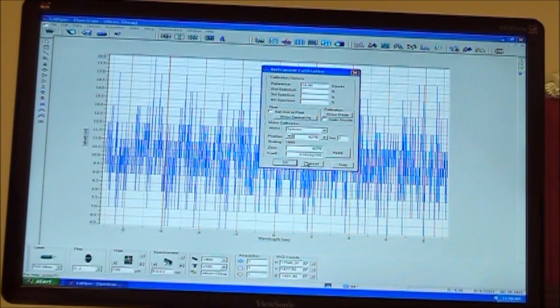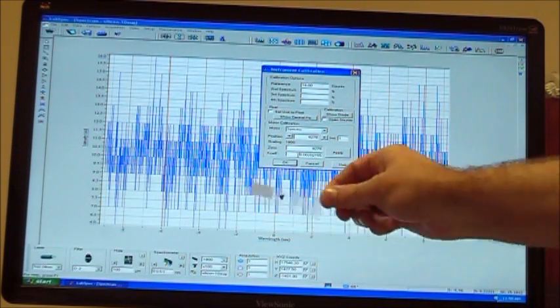So once you are sure that your 0 laser line is actually on 0, because that is the start point for all the calculations, and if that is not right, none of your peaks will be in the right position. After that, there is a coef adjustment for a spectral peak.